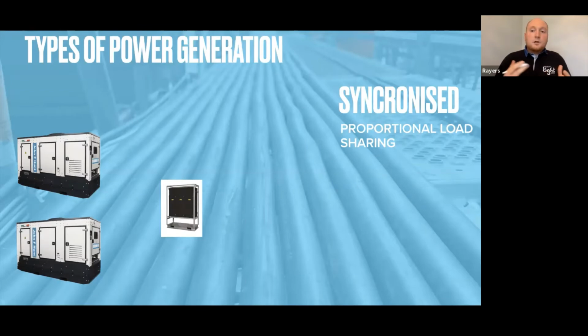So what proportional load sharing allows us to do is to take the same scenario as what we had before. And bear in mind, this doesn't have to be 2 machines. This could be 4, 6, 8, 10, you know, whatever. But it allows you to take a number of machines of one size and then add, if you just skip to the next slide, Meg, I think it brings up a little generator. There we go. To add another generator of a smaller size and link them similarly as we have done previously into one common bus, the distribution board you can see there.